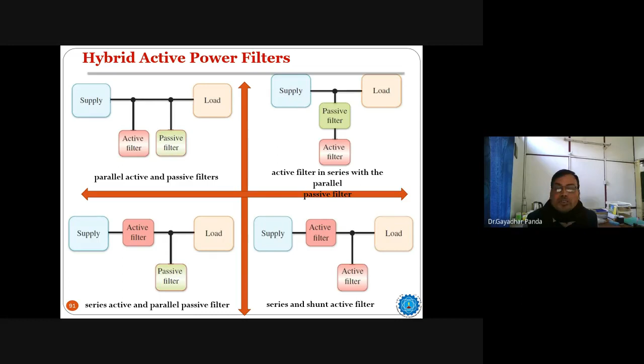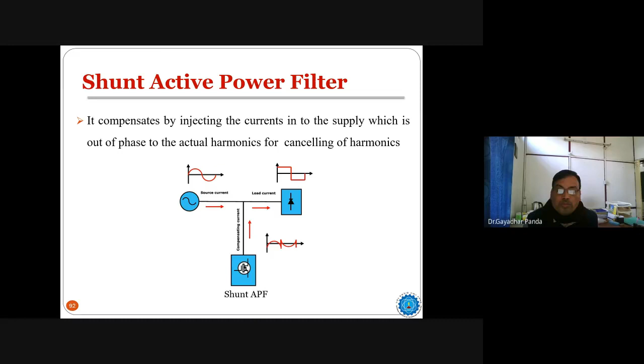These are the different topologies of the active power filter. If the power filter is connected in parallel to the load, it is called a shunt active power filter. This is a detailed diagram. You can see how this shunt active power filter is connected here. The active power filter is nothing but an inverter with a DC source, and that DC source can be replaced by a PV also. Your three-phase source can be considered as a utility grid, and here a nonlinear load is connected.